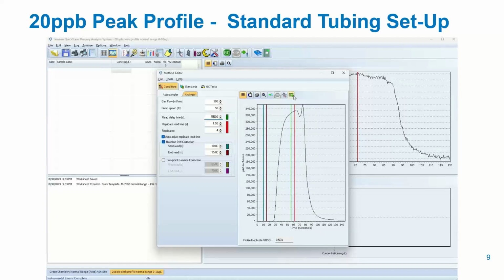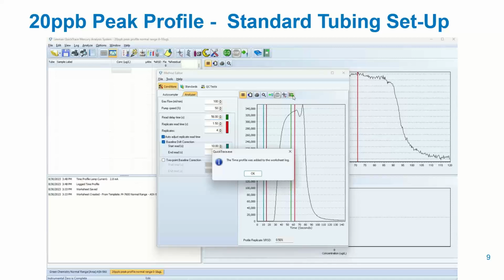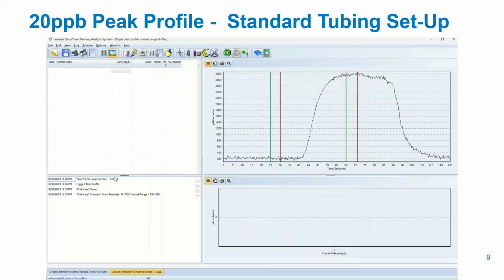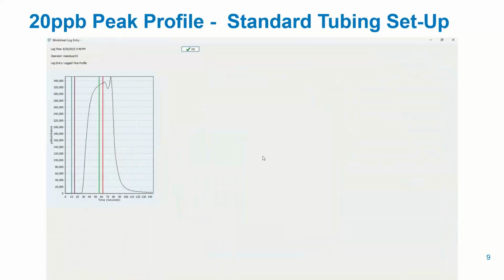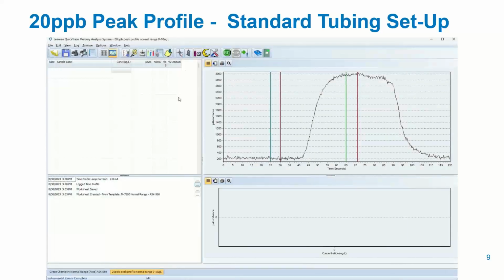So now that we're happy with our new method, let's save it to the log. So this keeps a record of the lamp current, the peak shape, the timing, when the chart was saved. So it's a great reference to have, especially for troubleshooting, because you know what things look like when they were good when you first started. So down here, click the ellipses, and you can see it full screen. All right, so that was our peak profile using our standard tubing and a 20 ppb.